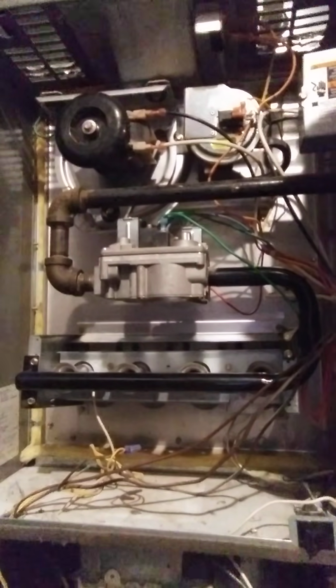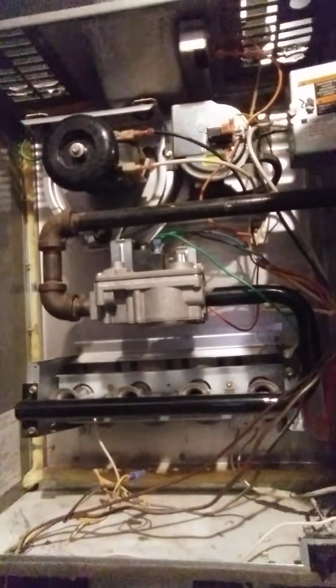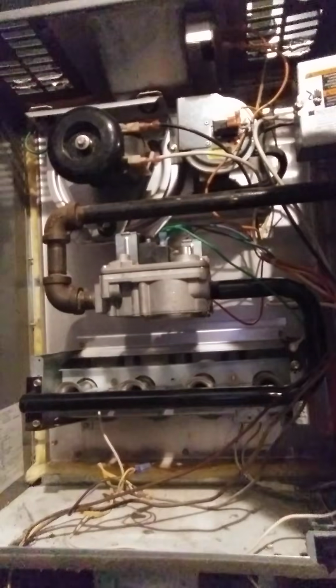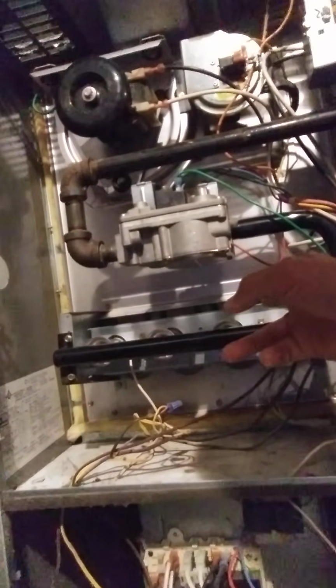Okay, so you have a couple different sensors going throughout the appliance here, and one of them is a flame rollout sensor. Basically it detects flame that's rolling out from the flutes and coiling back, and it's not able to go straight into the heat exchanger. And so the system will shut down in a case like that, or if the flame rollout sensor is bad, because it does not want the flame rolling back and frying any of the actual inner components of the heater. The flame should be going straight in through the holes that you can see that actually go into the heat exchanger. There's also other sensors and things around the unit, and those have connections as well. You see a few of those.